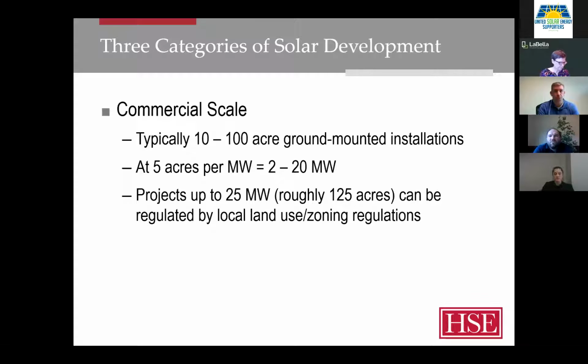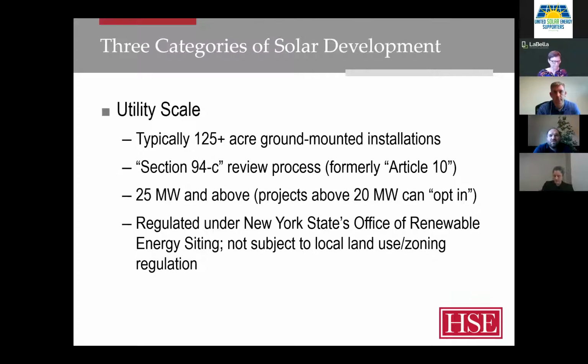The main category we'll talk about today is the middle category: commercial scale solar farms. Typical size is in the 10 to 100 acre range, though that's not a hard and fast rule—just what you typically see. As a general rule of thumb, which has changed over time, it takes roughly 5 acres to produce a megawatt of electricity, and that figure has shifted as technology improves, and will likely keep changing. So a 10 to 100 acre range gives you roughly 2 to 20 megawatts. Once you get above that, say 25 megawatts or more, you're in the third category: utility scale projects.